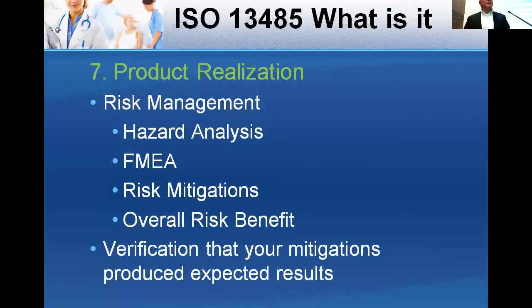A failure mode and effect analysis. You do this during your design process, do it again during your manufacturing process, because your manufacturing process may introduce new failure modes into the device. Your risk mitigations need to be checked and verify that they actually mitigate the risk and produce the expected results. And you're only going to know that after you build your alpha prototype and you start doing some testing.